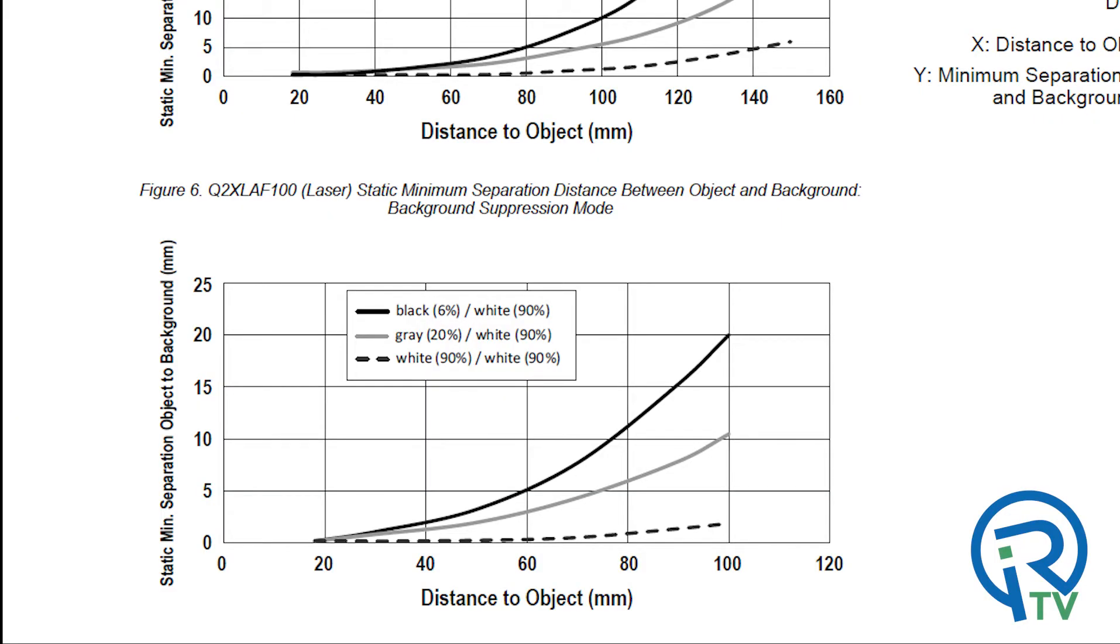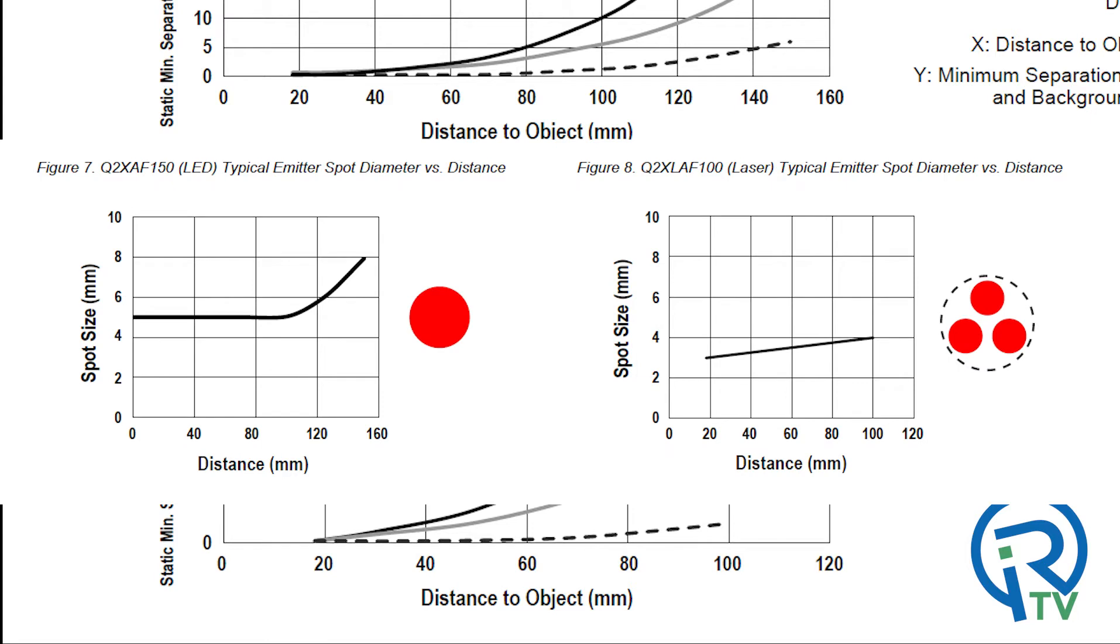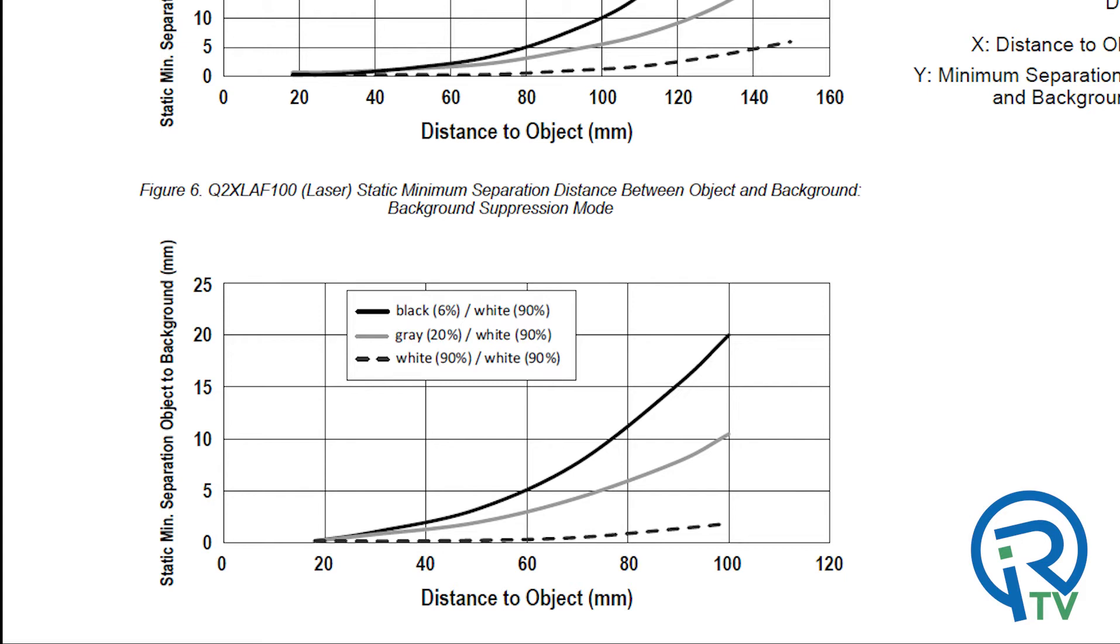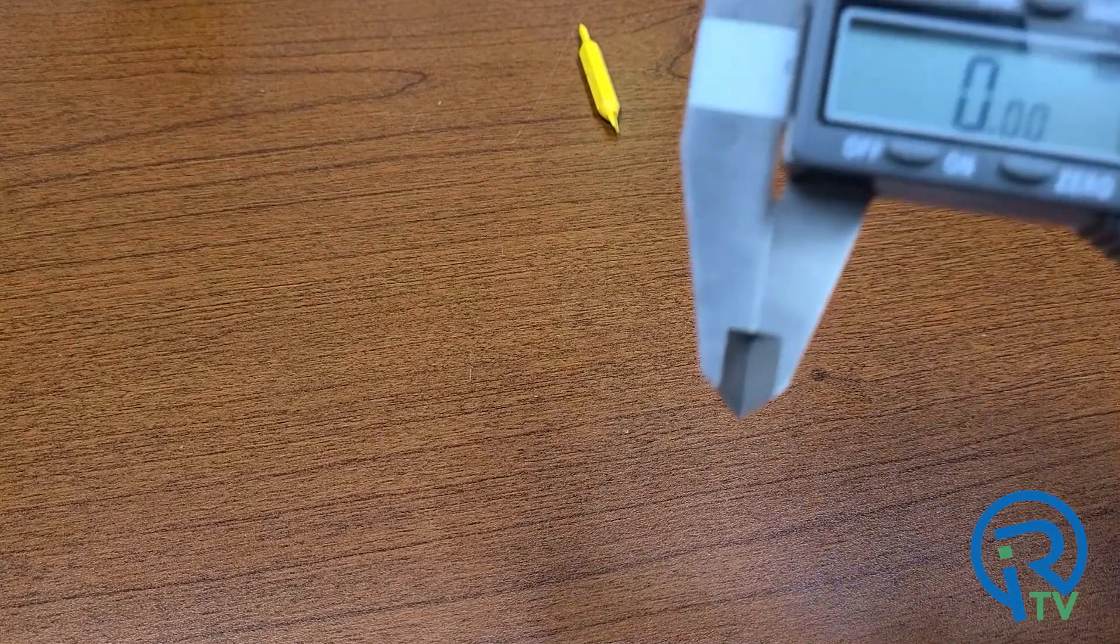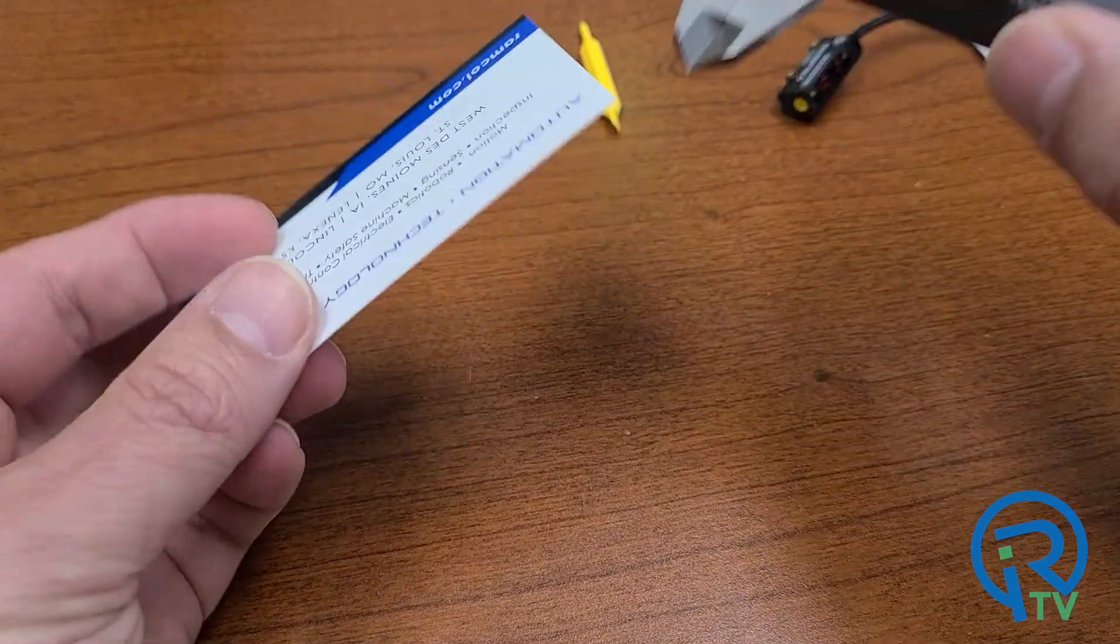Let's take a quick look at the laser version now. The laser version has a smaller spot diameter. The beam is essentially 2 to 4 millimeters depending on the sensing distance. The range is from 20 to 100 millimeters. The performance curves are very similar to the LED version. Let's throw something really challenging at the laser version and let's see what it can do. I have two business cards that are roughly 0.70 millimeters thick.